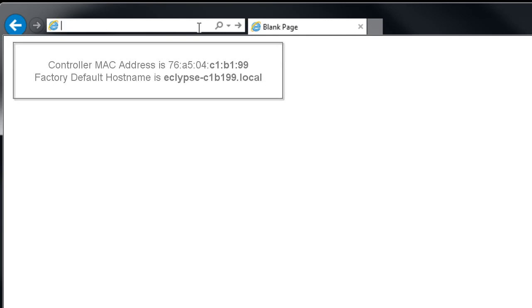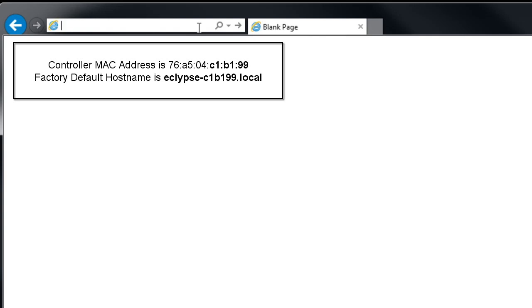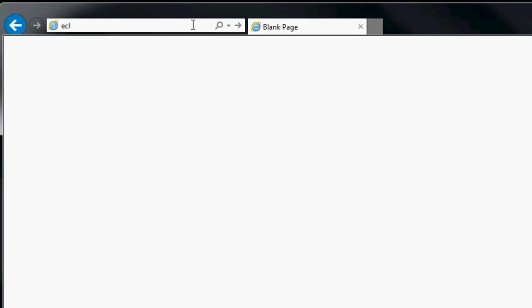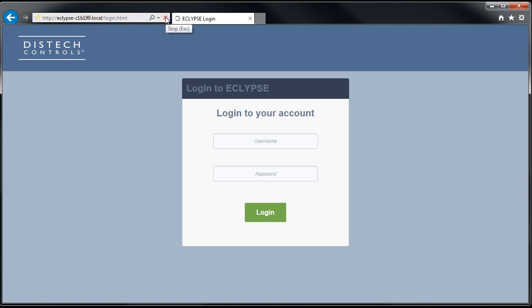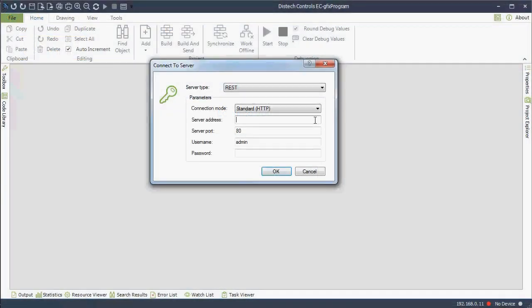In the web browser's address bar, enter the controller's factory default host name followed by .local. For example, the MAC address shown on the controller or the shipping box is 76-A5-04-C1-B1-99. Take the last six characters of the MAC address so that the factory default host name becomes eclypse-c1b199.local. Then click Go. This host name can also be used when connecting to the controller with ECGFX program.